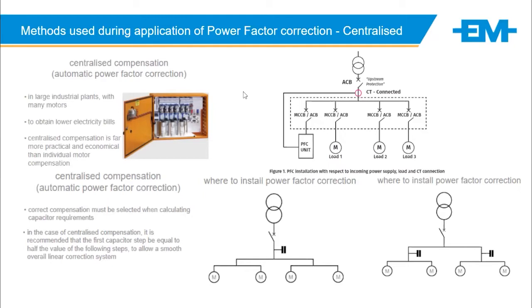Okay. So where would you install it? It really depends on your problem, but most common is closest to the point of coupling with your council, because that would be closest to where you're getting billed from. All right. Some customers may move the PFC system further down into their plant. The reason for that would be to reduce the demand on cabling. So if you've got a bad power factor in maybe a certain warehouse, which has got some machinery, which is away from the transformer, it may be better to put it there if you're having some cable heating issues due to bad power factor or high demand. Okay, but in most installations, it's as close as possible to the coupling of the utility.